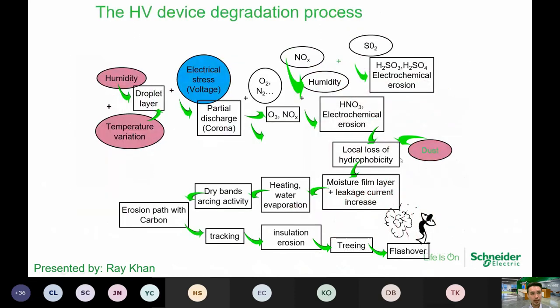So over a period of time, dust starts to accumulate inside the panel, because the insulation is making use of the ambient air. The buildup of this dust will also cause the loss of hydrophobicity. What it means is that the insulation will wear off at a much faster rate. Once the insulation wears off, the ability to repel water is not there anymore. All right, so there will be water pooling on the surface layer. And then this will lead to issues where tracking and also corrosion start to take place. And once it gets more serious, it will start to form treeing like the photo you saw earlier. And then one day, there will be a flashover. Okay.